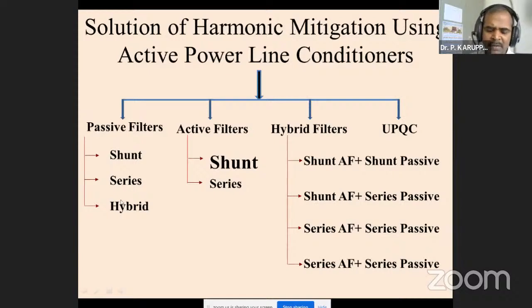So if you look at current harmonics versus voltage harmonics, 90% of the problem is current harmonics only, because that is directly relevant to the load. So here the shunt filter is the suitable option.